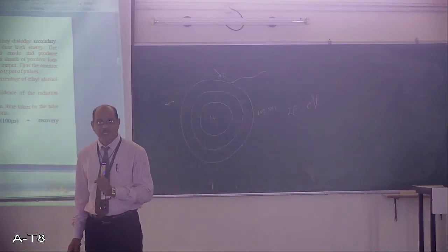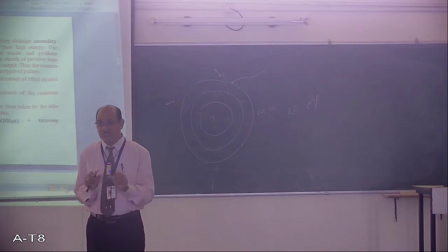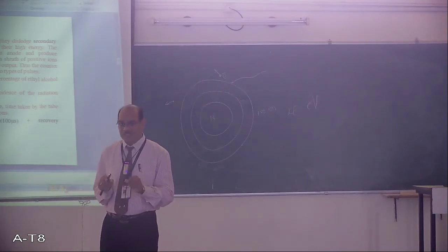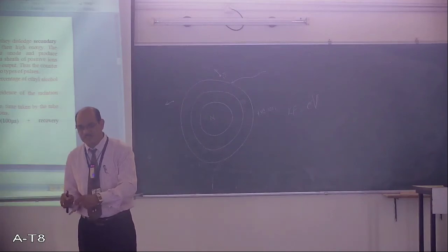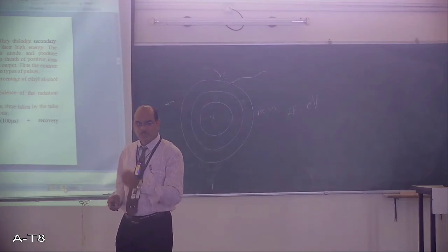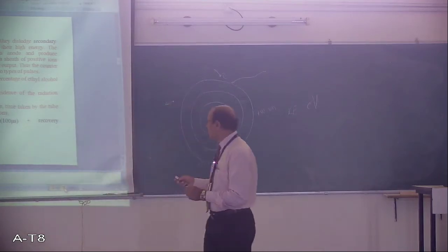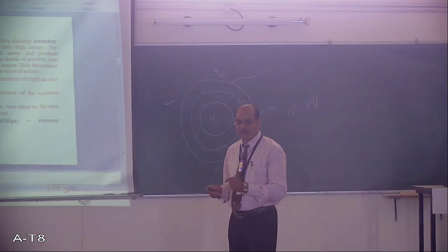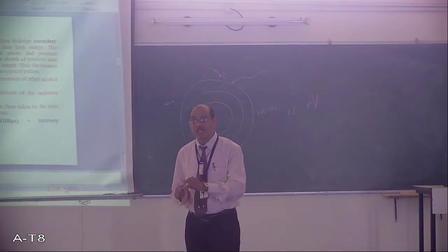It means that in between the first pulse and the second pulse, during the dead time, even though the incident radiation particle is entering the tube and colliding with the argon atoms, that particle will not be registered.